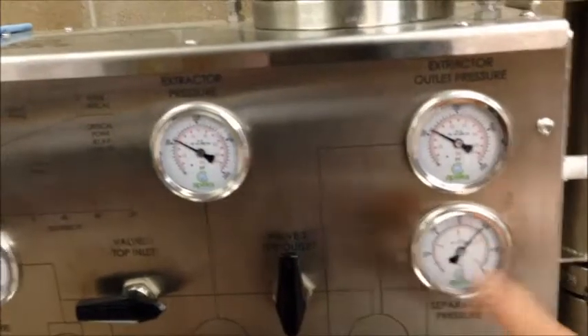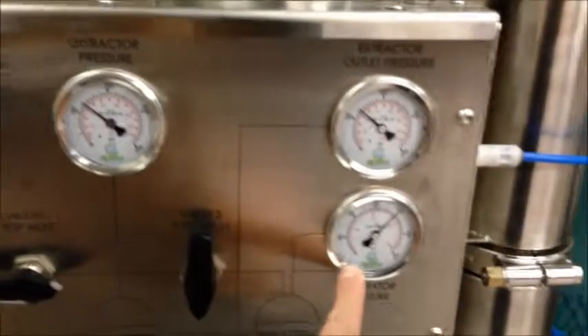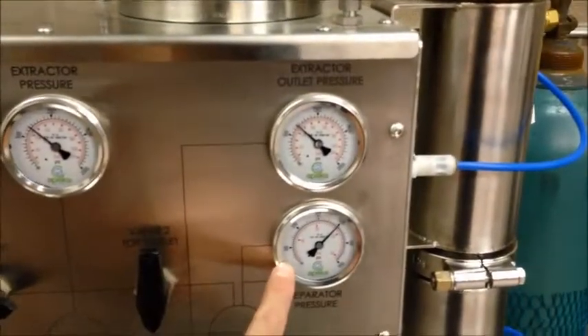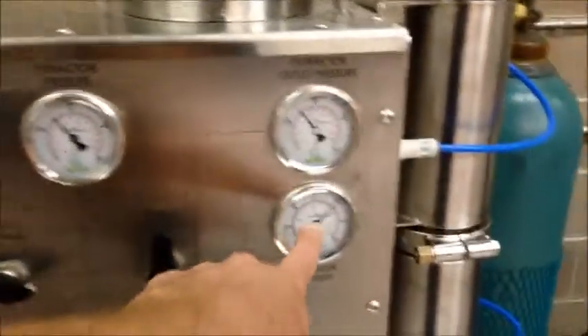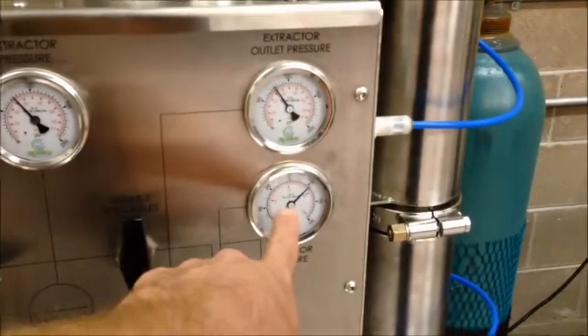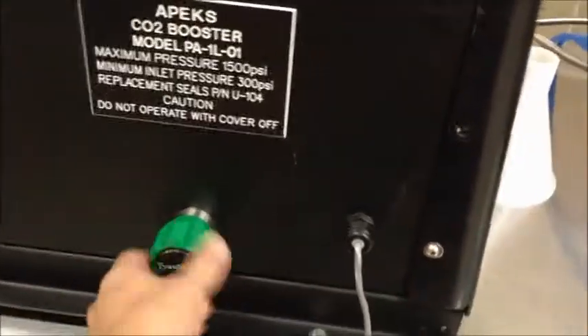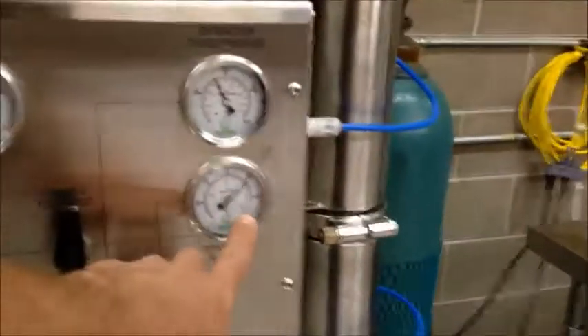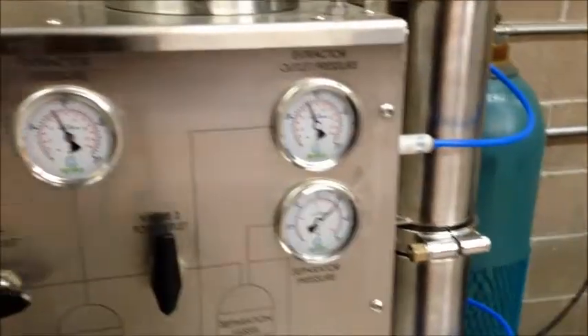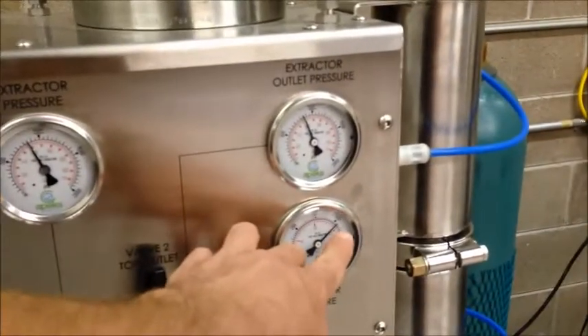So now what we want to watch, we want to try to keep this around 420. It takes a few minutes to stabilize. As you can see, as this climbs, this is also going to climb. This is your extractor, here's our separator. So right now this is at 400. I'm not going to mess with my green valve just yet, but as this climbs, I need to watch and make sure this stays around 420. If right now it's not at 400, I would come over here and increase or decrease to bring this either up or down. So if I was at 475, 450, I'd decrease. If I was down here at 300, I'd increase it, get as close to 420 as possible.